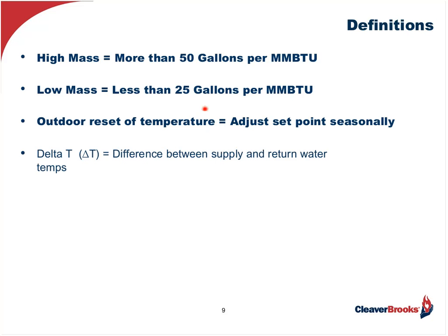Delta T, this is the temperature difference between the supply and return. Now, the important thing to remember here is the higher the delta T, the lower your energy consumption. Years ago, we typically designed systems using a 20-degree delta T. This was mostly to protect the boiler. Nowadays, if you want to design a high-performance system, you really want to be looking at a 30 or 40-degree delta T. And it's not so much that it's the delta T that's saving you energy. It is, because if you double your delta T, your GPM goes down by half. So that's going to save you pump energy, but it's also going to give you colder water to the boiler, and as you'll see later on, that's going to improve your efficiency of the system.